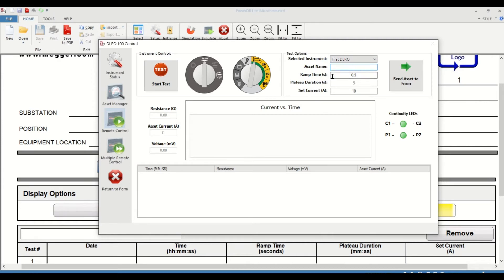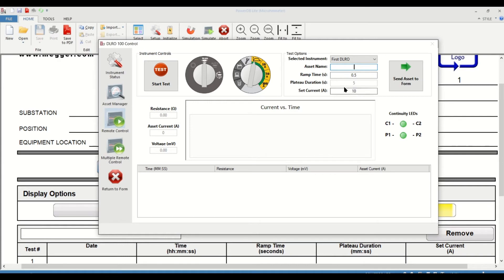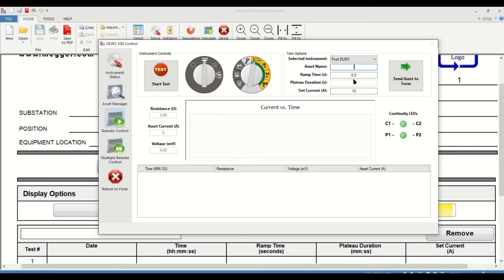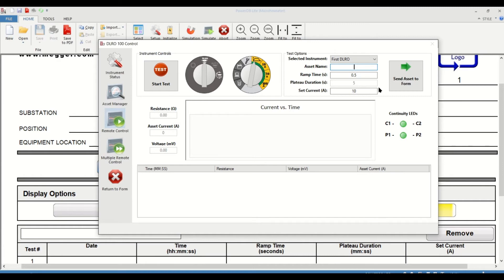Now the ramp time is the time it takes for the DLRO to reach your test current magnitude. So for example, if the set current in this case is 10 amps, it'll take 0.5 seconds for the test current to reach a value of 10 amps. And the plateau duration stands for the amount of time for which that current will be injected in the test specimen. So once you initiate the test, it'll take about 0.5 seconds to reach a 10 amp value. And that 10 amp value will stay constant for about 5 seconds before the test begins to ramp down, and then finally, the test ends.